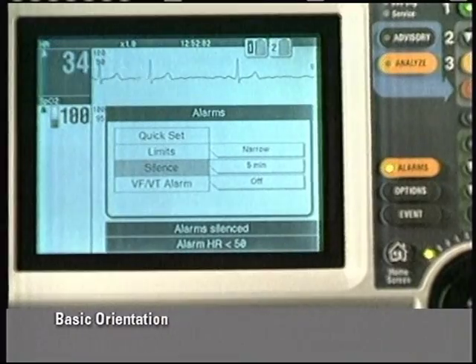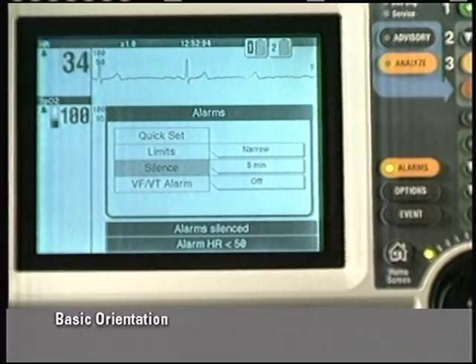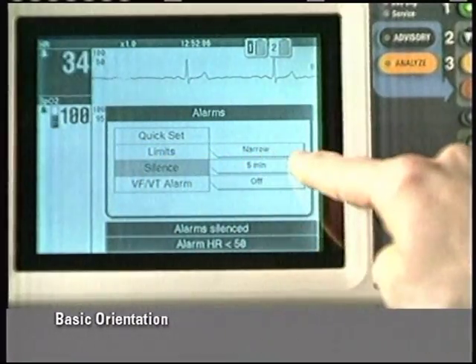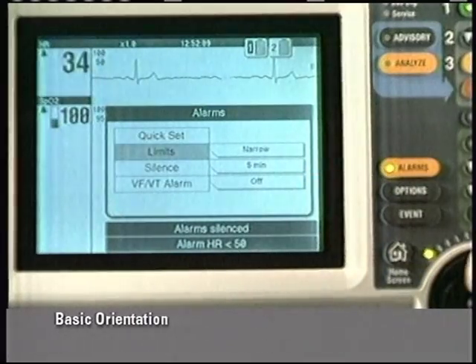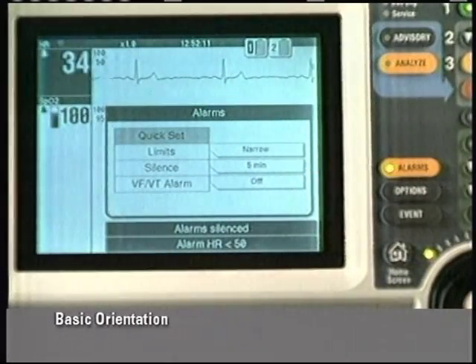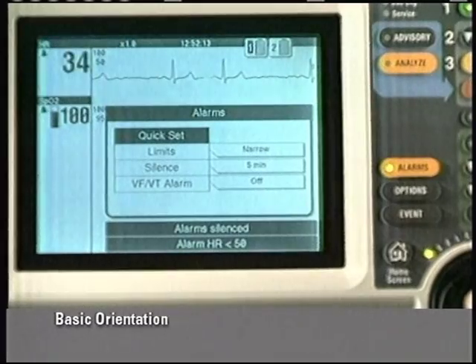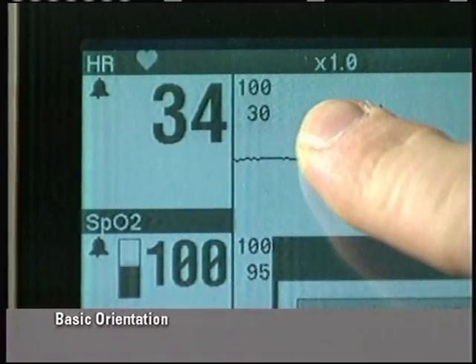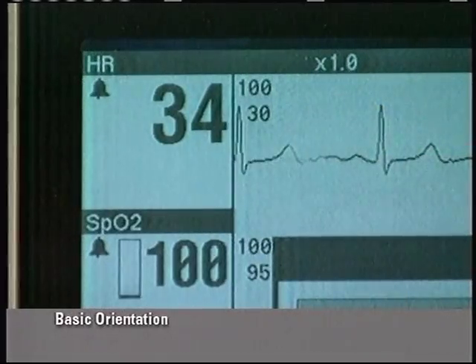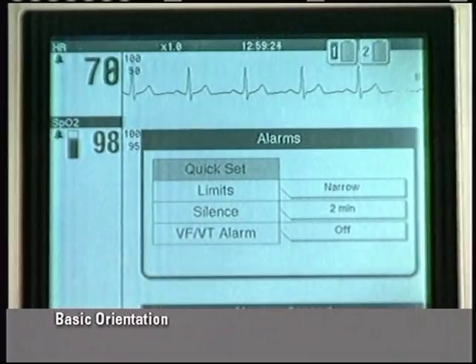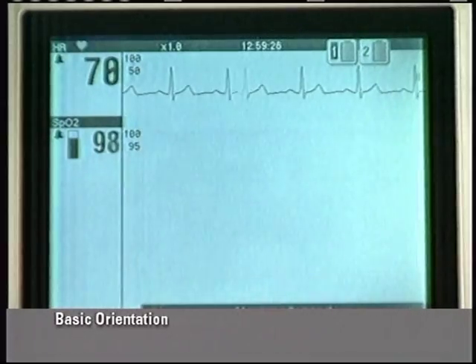Next, assess the cause of the alarm and whether narrow limits, if selected, should be set to wide. If the patient is unstable, do not reselect QUIK-SET. Reselecting QUIK-SET resets the limits around the patient's changed vital sign values. This may be outside the safe range for the patient. Only after the patient is stabilized should you reselect QUIK-SET if necessary.